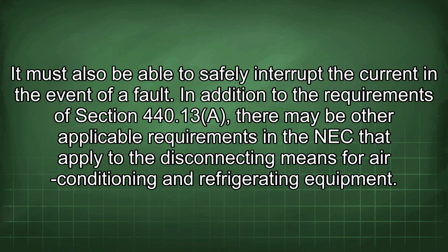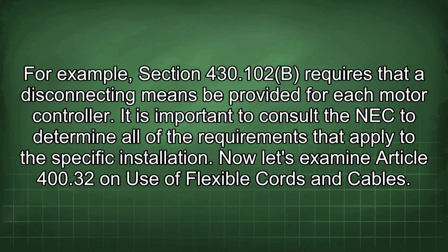In addition to the requirements of Section 440.13a, there may be other applicable requirements in the NEC that apply to the disconnecting means for air conditioning and refrigerating equipment. For example, Section 430.102b requires that a disconnecting means be provided for each motor controller. It is important to consult the NEC to determine all of the requirements that apply to the specific installation.